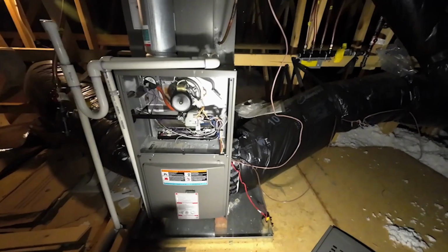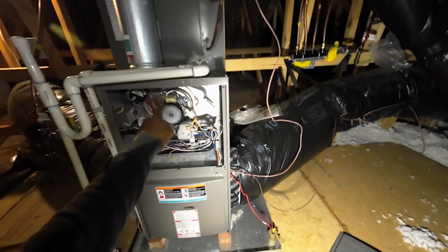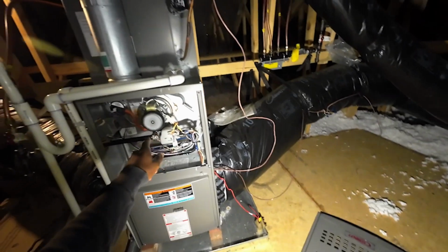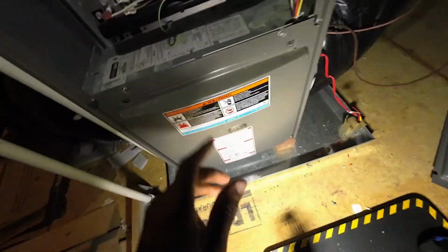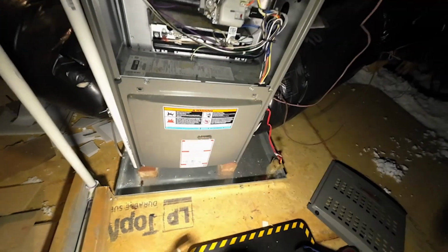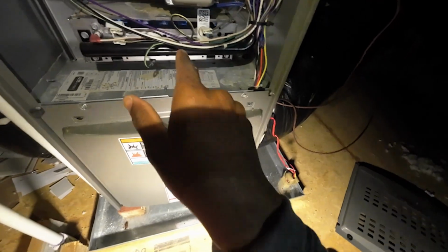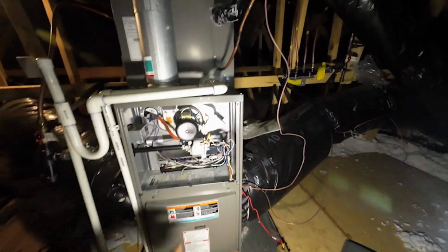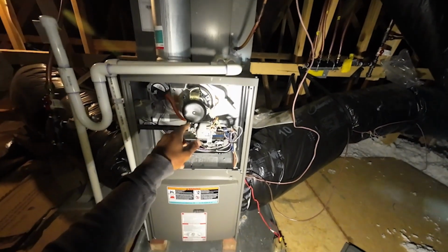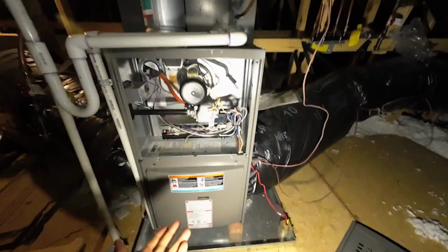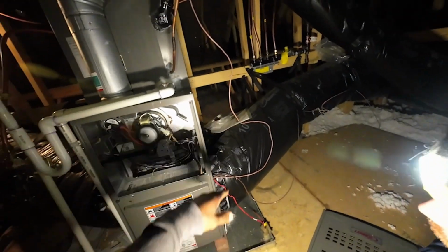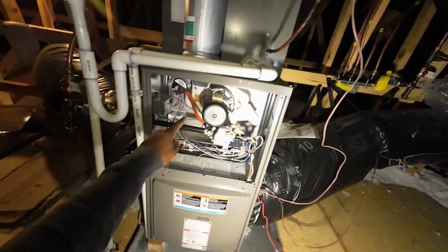I'll show you. I'm going to check my amps on the inducer motor. This is the inducer motor. This was causing the exhaust gases. If you look down through here, you can see the flames. Yep. They're being sucked down into those holes. That's because this inducer motor has an impeller in there, and it's pulling the flame up through pretty much a serpentine type heat exchanger, and then it's forcing it up through here.